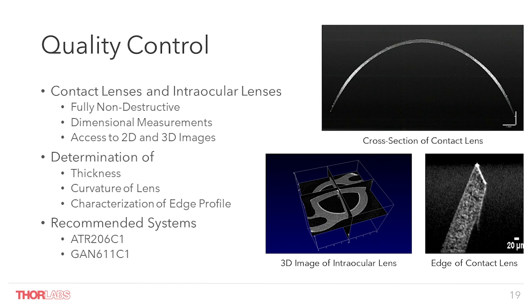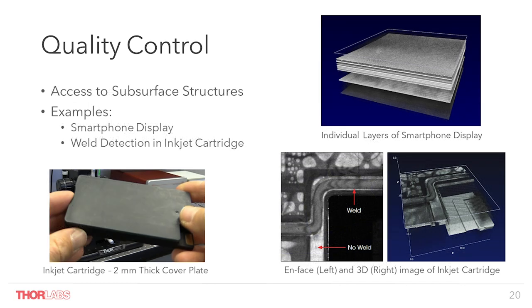An already quite well-established application of OCT is its use as a quality control tool for contact and intraocular lenses. With OCT we can get high-sensitivity images of these normally quite transparent devices, and this allows dimensional measurements to be taken in an automated way — for example, analyzing the thickness and curvature of contact lenses. If we zoom in with a high-resolution setup, we are also able to get a good impression of what the lens edges look like.